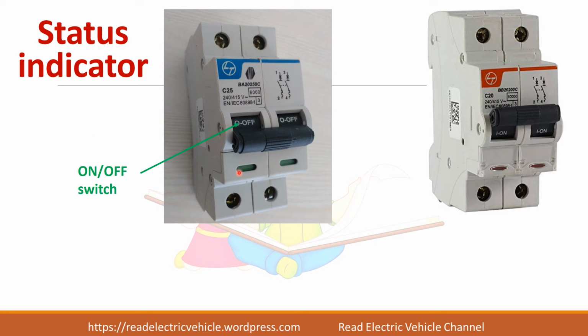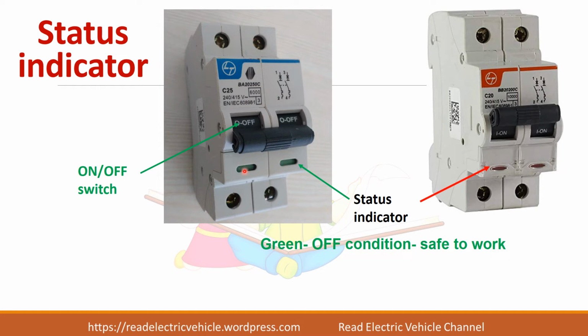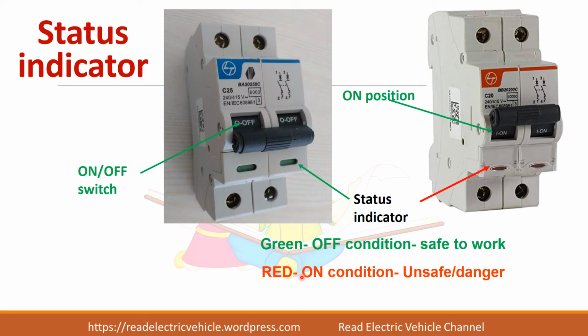Now there are also, in addition to this on off switch, two things here which are called status indicators. So here this is in green color, here you have it in red color. So this breaker is in off position. Green means off condition. It means that it is safe to work. But here you see it is in red color. This breaker is in on position. So red color means on condition. So it is unsafe or dangerous to work with this MCB.